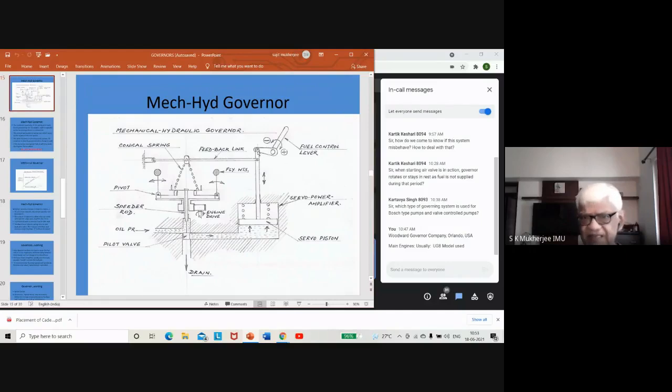If it fails from this link, the governor may give a signal to shut down the engine, but the fuel rack, which is under a different spring load in the maximum position, will automatically go into the maximum position. Because this pin is no longer holding, and over a period of time, this pin can get sheared off because it is the most neglected pin on board the ship. Nobody looks at this pin, and yet it is the pin that is holding the entire engine injection process by the governor. If this pin fails, you can have runaway engines.